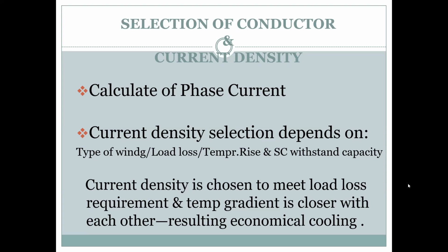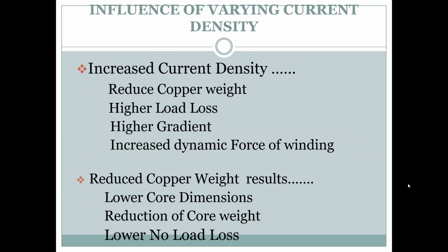But your requirement is that for this project, you need a transformer that should work for its lifetime, say 25 years, 30 years, with this much loss, this much temperature rise, whatever the specification is. But who are you to dictate my design? So these are the pressures on the transformer manufacturers. And still, my first general manager told me the customer is always right because he has got money. So we follow that. Yes, I'll give you. So we lower the current density. Lower current density means more copper.